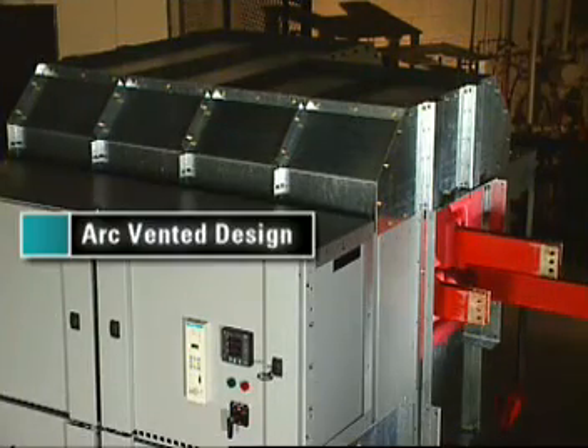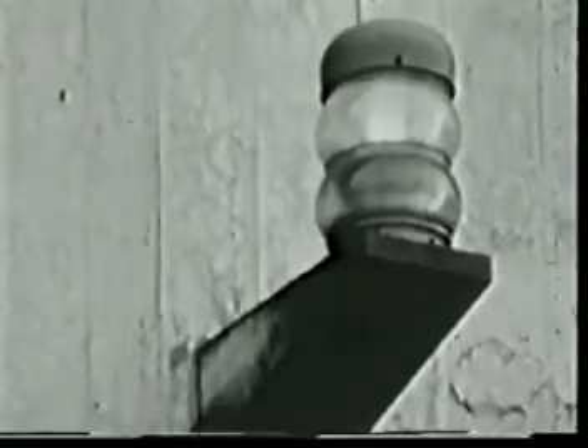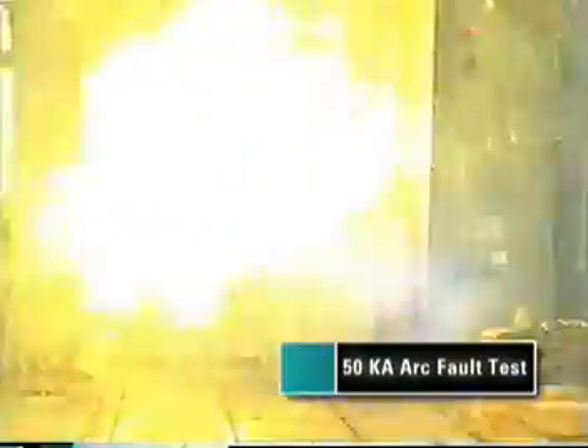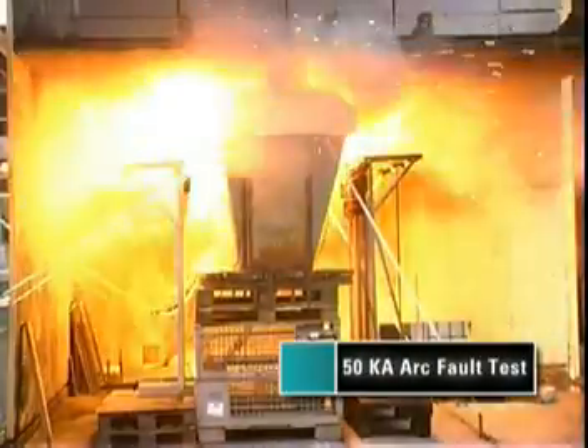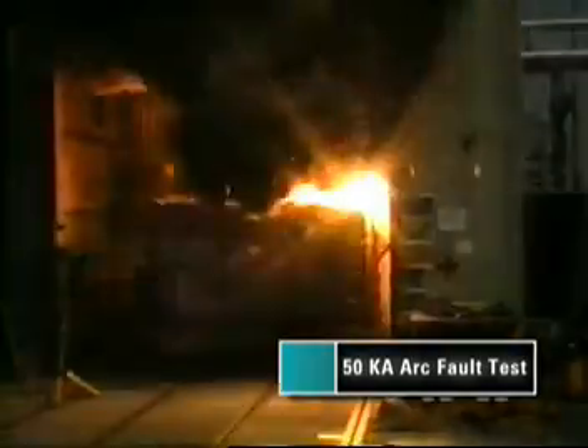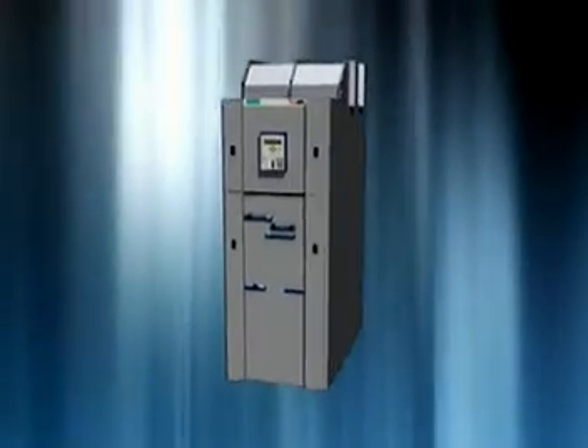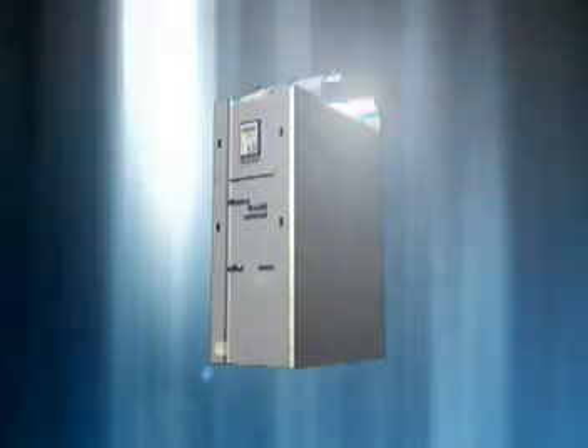Operator safety is another major concern for our customers, making arc-vented equipment more important than ever. Siemens has been doing arc fault tests for over 25 years, which resulted in the design of the NXAirP. While arc events can't be completely eliminated, switchgear can vent the arc away from the operator. We say that the NXAirP is arc vented rather than arc resistant because if an arcing fault occurs, it is designed to handle it in the safest way possible. In the event of an arcing fault, the NXAirP directs the arc and hot gases upward through the top of the switchgear and away from the operator.